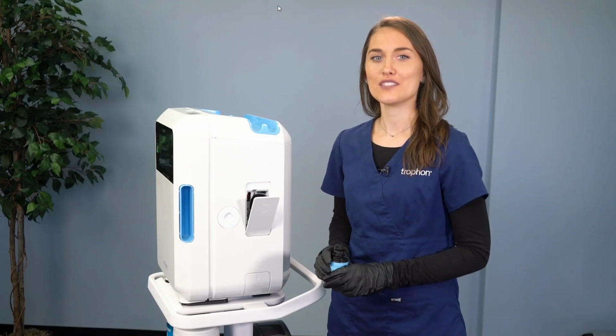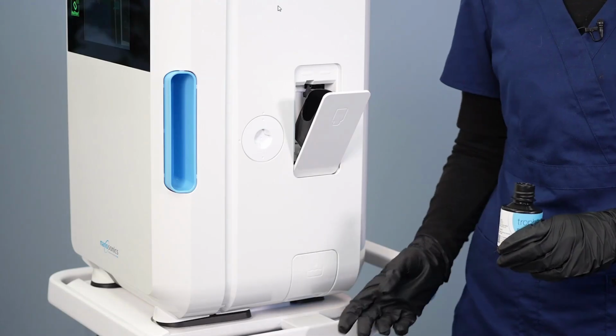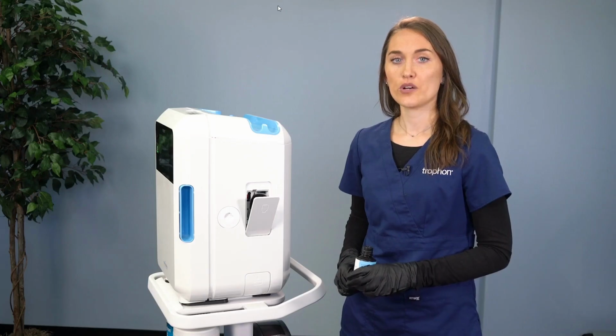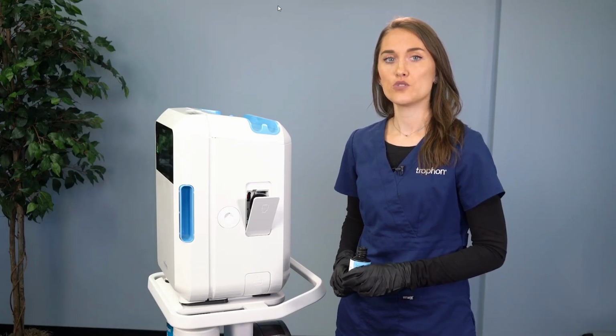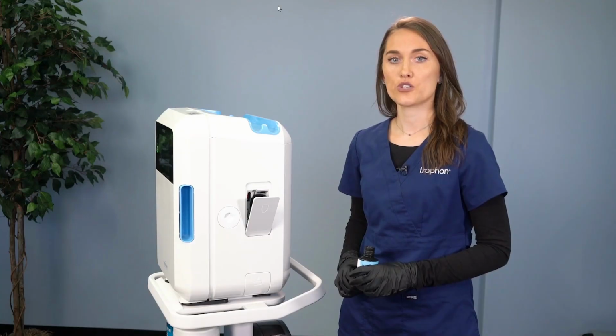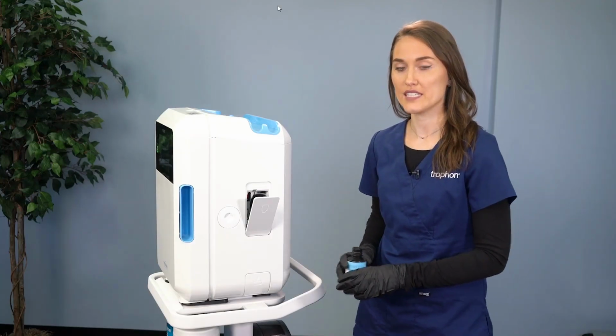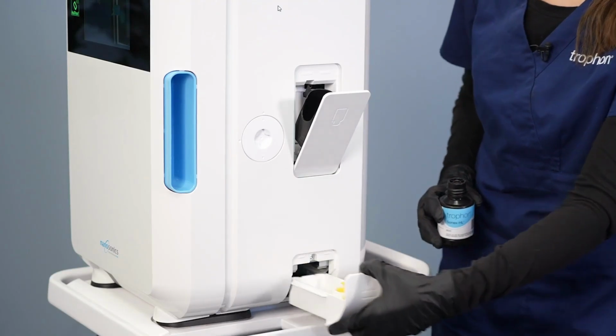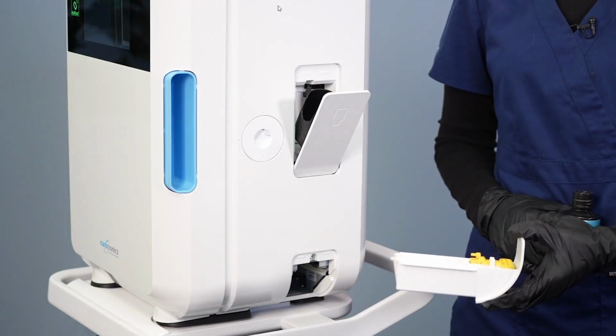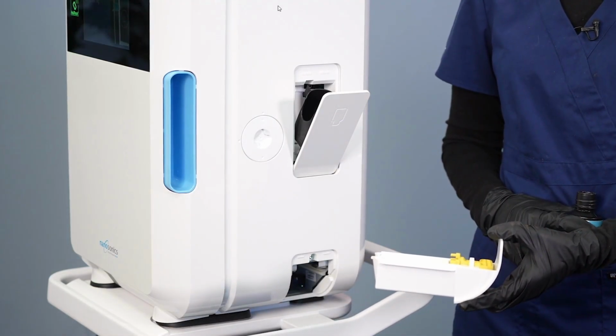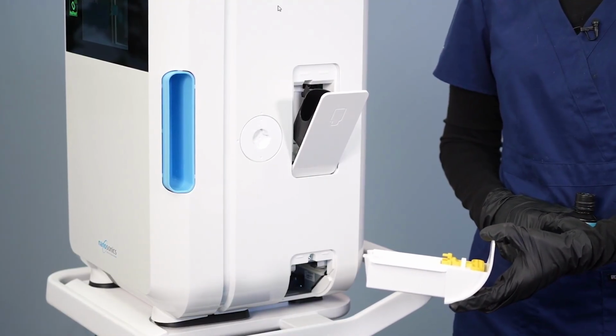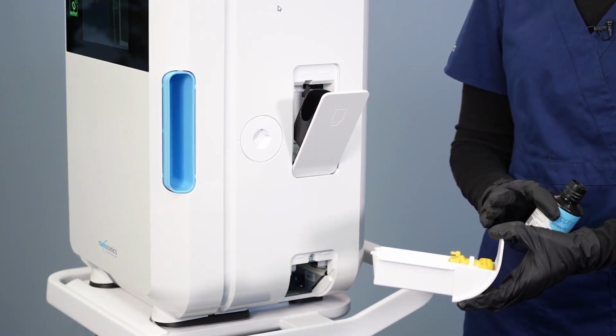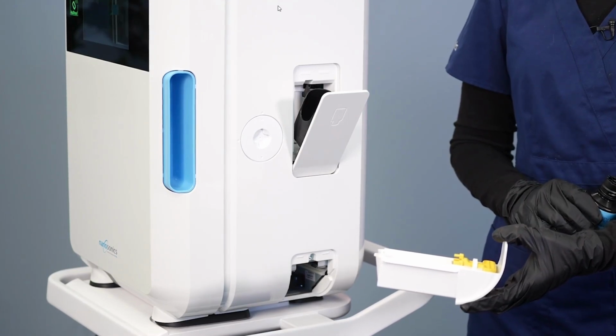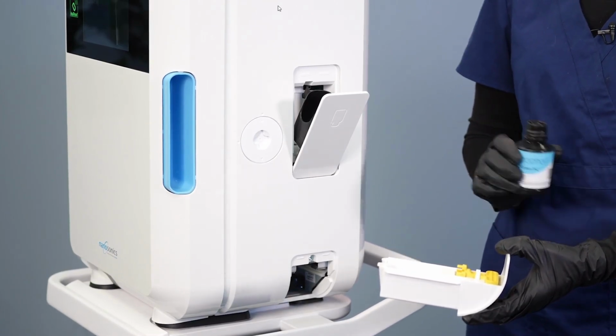The water will collect in the waste drawer located in the right side of the device. When purging is complete, the user will be instructed on the screen to remove and empty the waste container. The water from the waste drawer is perfectly safe to dispose of in the sink. Just rinse the container, dry it, and replace it. Then follow the prompts on the screen to replace the cartridge.